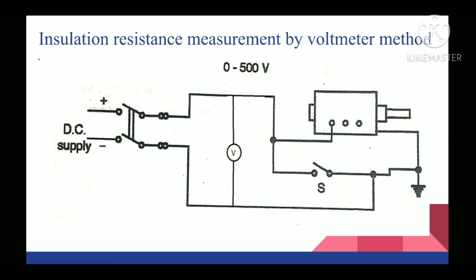A high resistance DC voltmeter with a range of 500 to 600 volts may be used to determine the insulation resistance, provided that the sensitivity of the meter is 100 ohms per volt or higher. Voltmeter readings are recorded with the single pole switch closed and with it open.